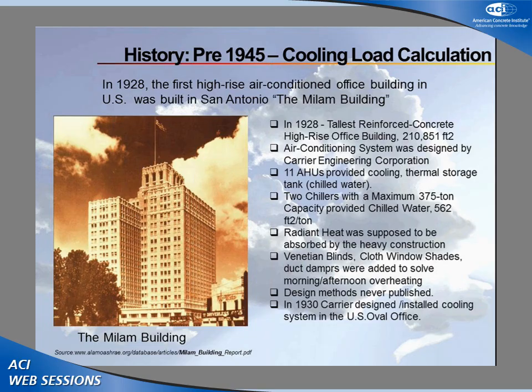They didn't know about thermal mass at that point, but they suspected a lot of the radiant heat would be absorbed by the thermal mass in the building. Unfortunately, after building and occupying it for the first year, they found big differences between the east side and west side of the building during early morning hours in the summer. So they had to split the system down the middle and put diffusers and duct diverters in, forcing all the air to the east side in the morning and the west side in the afternoon. All of that was done manually.